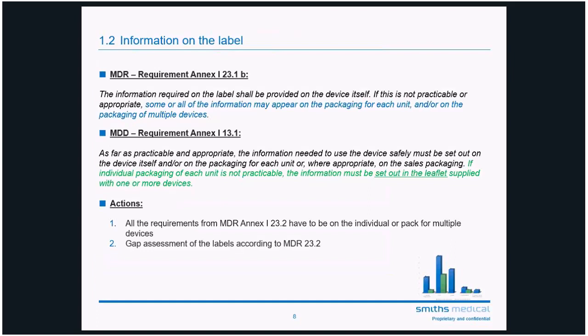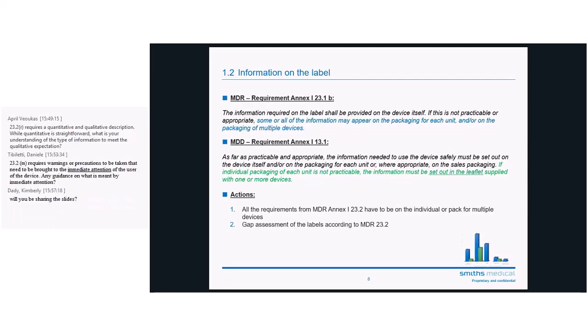The only caveat to that is what I have mentioned. It's no longer the instructions for use that could potentially carry that. So the answer to your question is Annex 1, 23.1(b), where that exemption or space limitation problem is discussed and resolved. This also covers the information to be put on sterile packaging, sterile barrier packaging. The sterile barrier is just a different form of your label, and that's how I would take that requirement. At the end of the day, it's labeling, and that's how I would read and interpret this requirement.